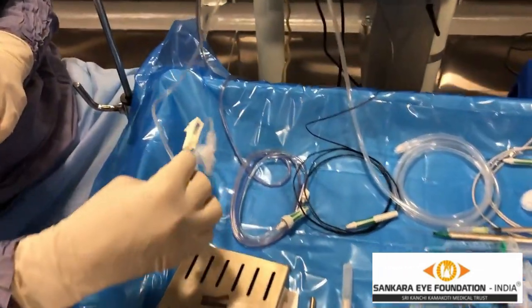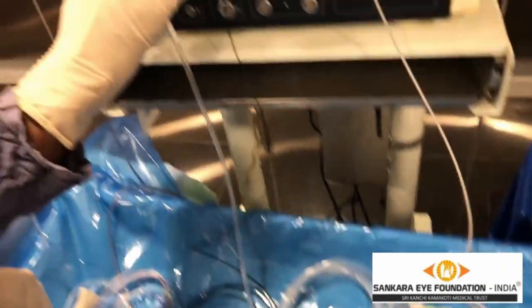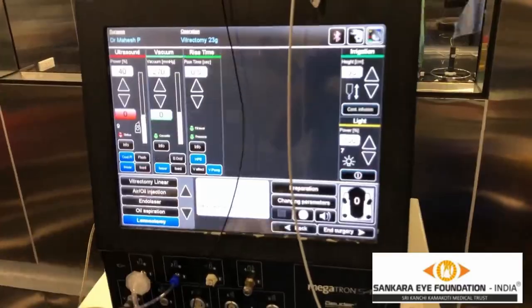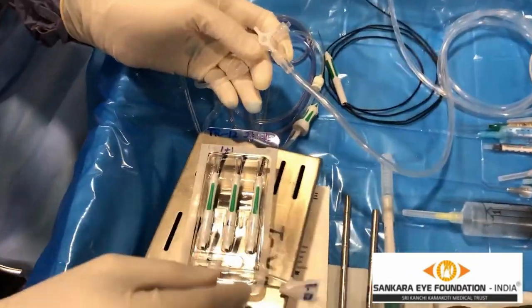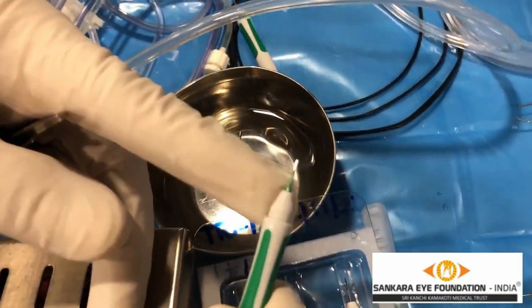Other important things are the infusion. As we can see, the infusion we are using is a gravity-assisted infusion; it can be a machine-assisted infusion also. There is a three-way where the tubings are connected. This is a vitrectomy cutter connected to the machine, with a cassette over here. This is a 23 gauge light probe, an air tube where the air is pushed from the machine, and a filter at the tip of the air tube. For connecting the air tube, we connect it at the 3-way. These are the trocar and cannulas for 23 gauge, with a sleeve.